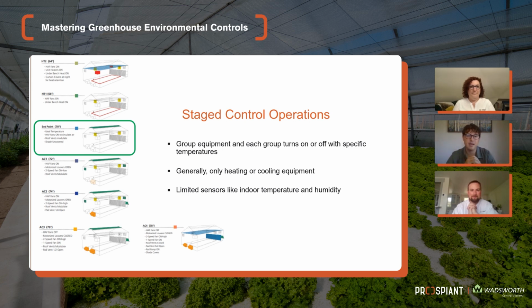So in this case, if we did have 6 heaters, we'd probably split them into groups, doing every other one to make it more of a uniform distribution of heat throughout the greenhouse. We'd do heaters 1, 3, and 5 for the first stage of heating. And as that greenhouse started to get colder, because maybe it starts snowing outside, we could then turn on the next stage, which would be all 6 heaters.